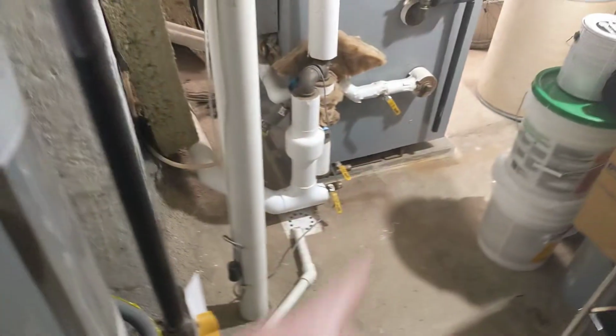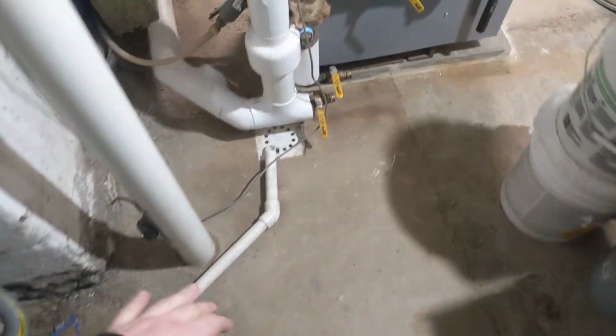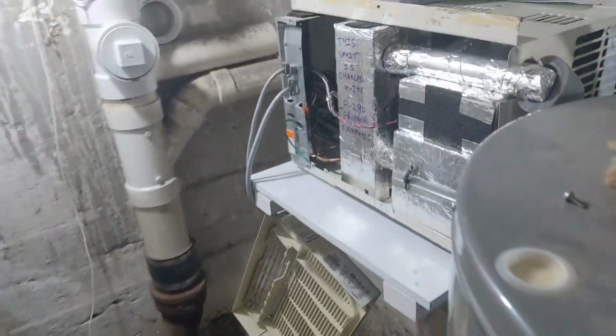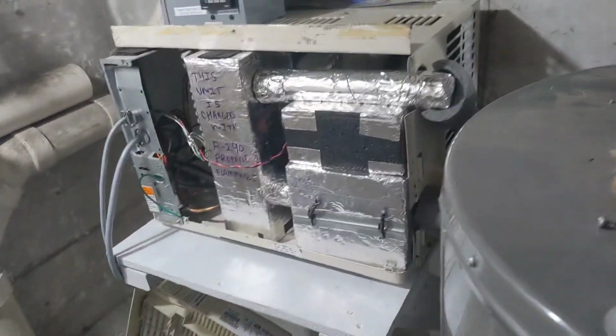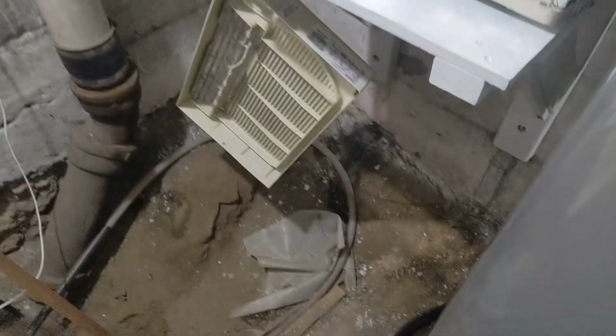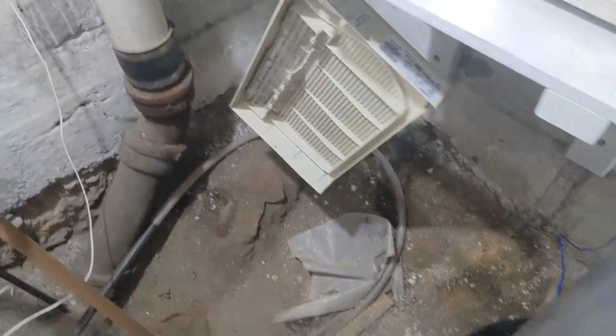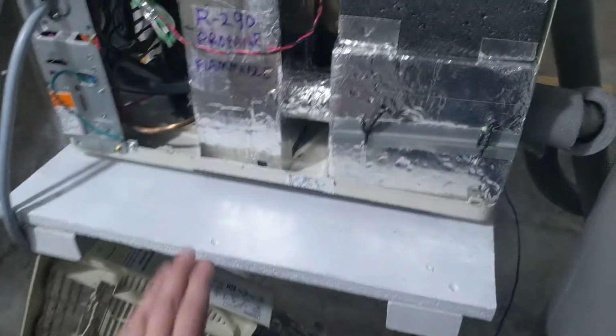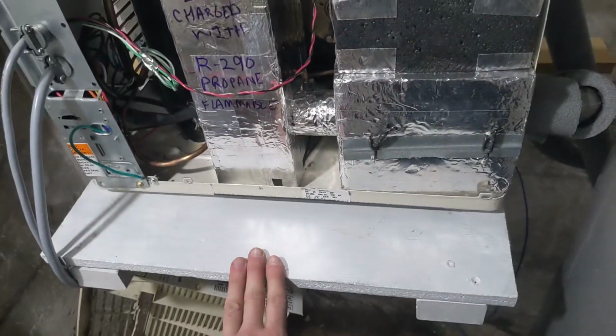We got our temperature controller. I'm still monitoring the temperature at the bottom of the tank through a thermocouple. It goes in right here. It's just shoved up in behind the insulation. It seems to work all right. So that's it. That's the change. We got it up off the floor and away from the boiler, out of the way here. So now I'm able to utilize this little cubby hole back here in the corner, space that otherwise would go to waste. You can see it's got a rocky, dirty floor in back here. So this was able to make use of this location.